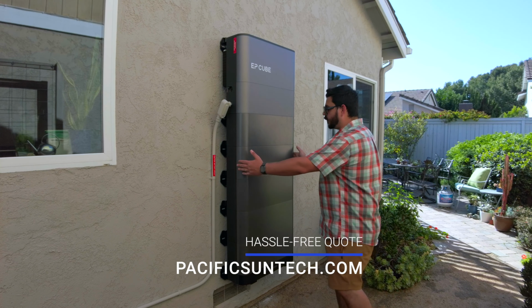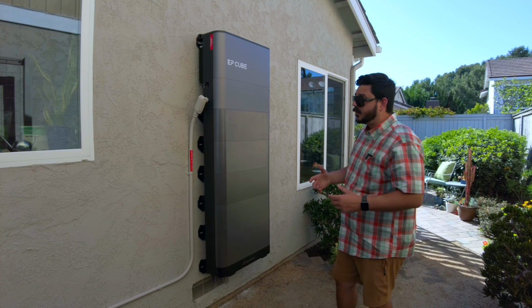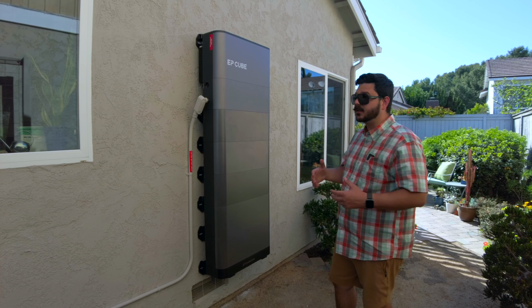Now in California, a lot of regulations have passed recently for the California residential building codes, as well as the California electrical codes, and they've basically handcuffed us in terms of where we can install batteries. Now this is an LFP battery, so it's lithium iron phosphate. It is UL 9540 and UL 9540A certified. So it is a very compact unit that has special certification. So technically it could be installed within 12 inches of a window or an entryway, but with these codes that have been implemented in the state of California, it's much harder.